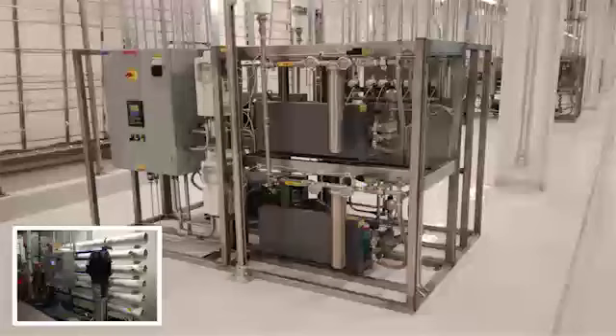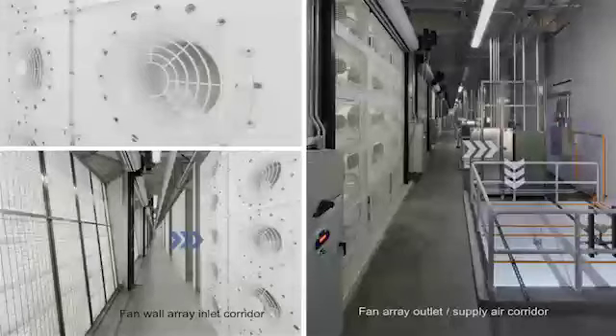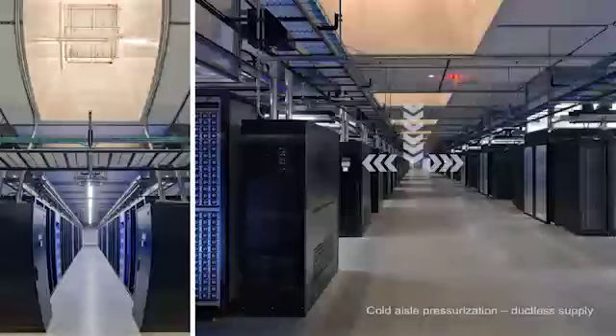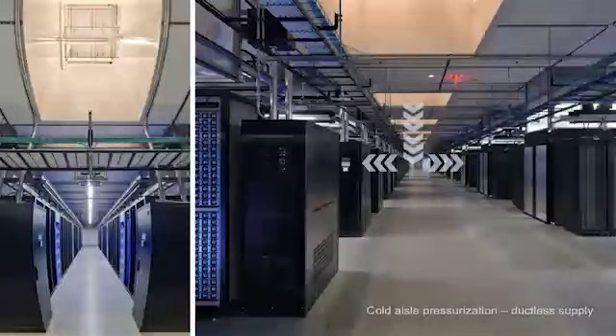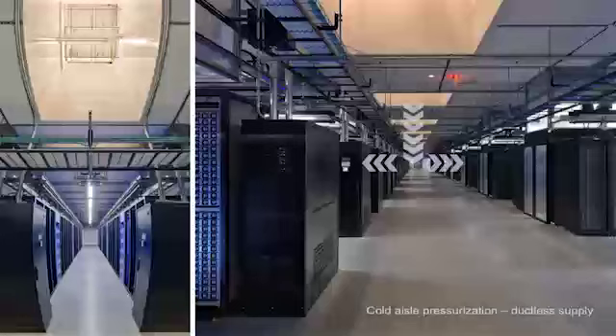Where we installed a misting system, we have our high pressure pump skids with multiple valves that control how much misting is occurring. And this is all based on outside temperature conditions and humidity. We then would use the mist eliminator to remove any carryover spray. Our fan arrays pressurize the supply air plenum corridor. The air comes down the data hall. The image on the left is kind of a fisheye lens view, but we've got the overhead supply opening from the penthouse, and we're looking down one of the cold aisles of our data hall.